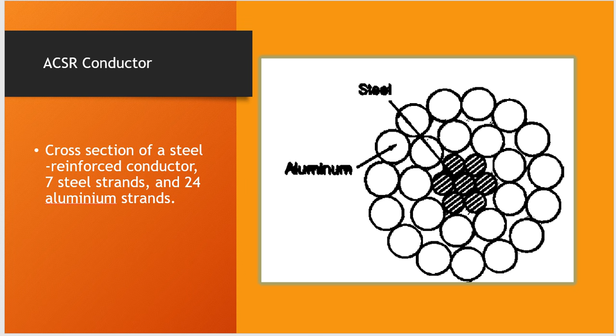It is having seven strands, sorry, not conductors. It is having 7 strands inside, whereas the two outer layers are made up of aluminium. And there are 24 strands of aluminium that are used for fabricating a particular conductor. So, in order to provide mechanical strength to the inner layer, we use steel, and we use 7 strands of steel, whereas for the outer transmission we use aluminium, and we have used the 24 strands of aluminium in this case.